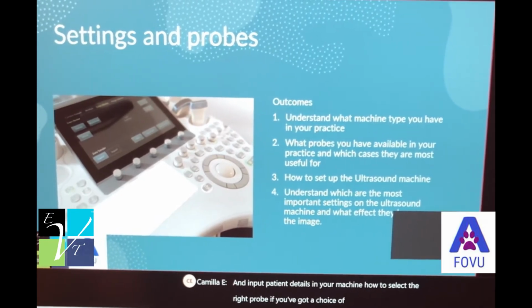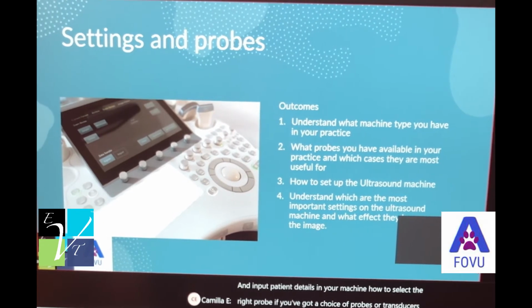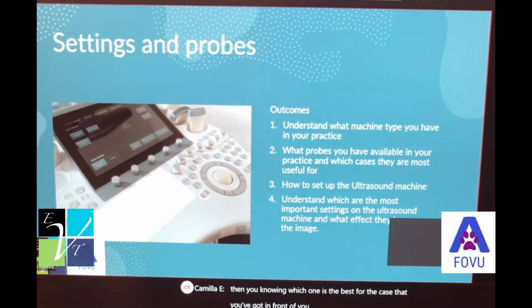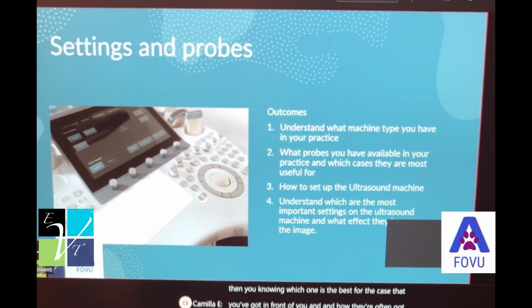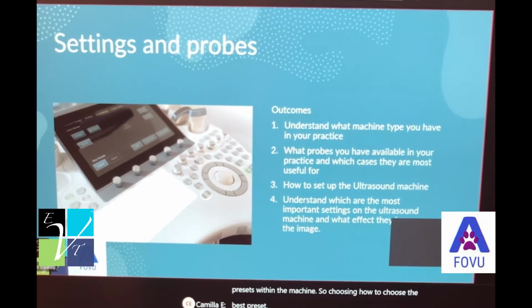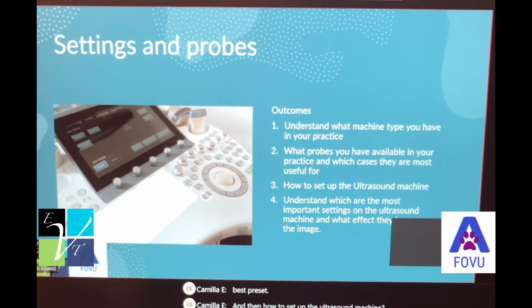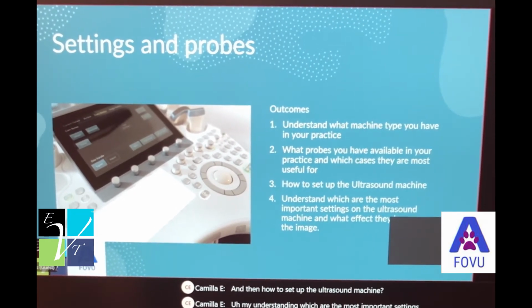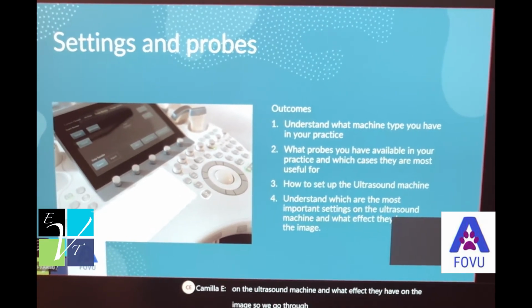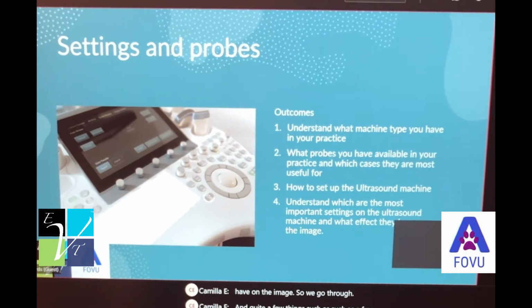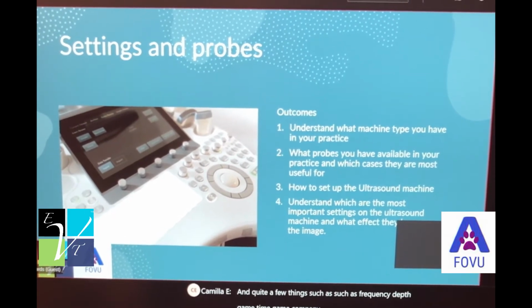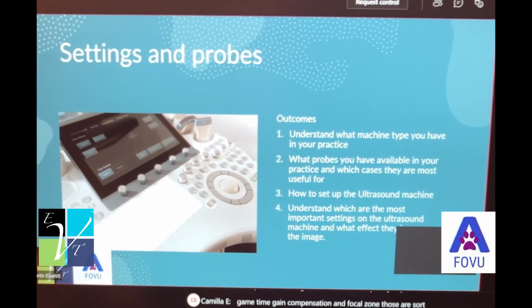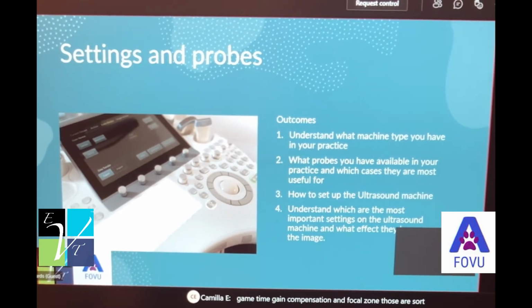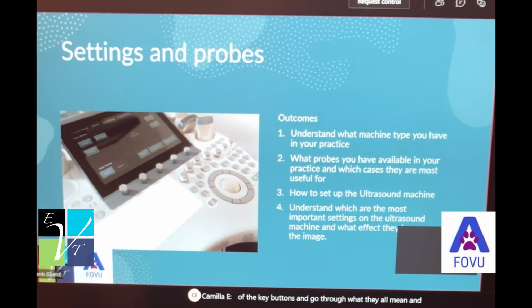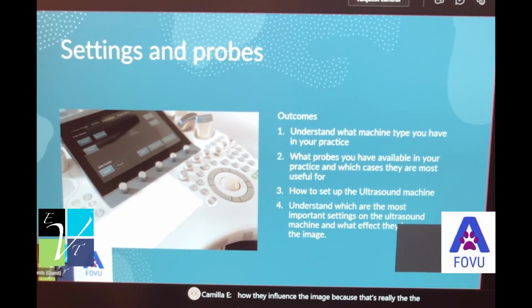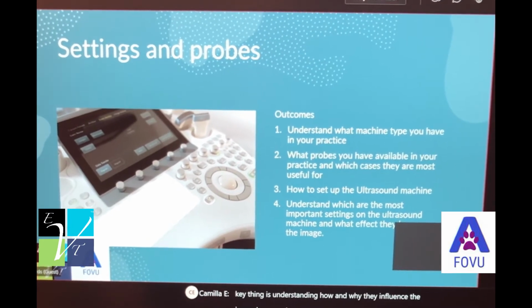If you've got a choice of probes or transducers, then knowing which one is the best for the case that you've got in front of you, and how they're often got presets within the machine, so how to choose the best preset, and then how to set up the ultrasound machine, understanding which are the most important settings on the ultrasound machine and what effect they have on the image. So we go through quite a few things such as frequency, depth, gain, time gain compensation, and focal zone. Those are sort of the key buttons, and we go through what they all mean and how they influence the image, because that's really the key thing, understanding how and why they influence the image, because then you can adjust them and get the best image possible.